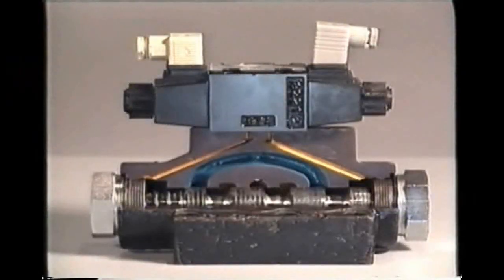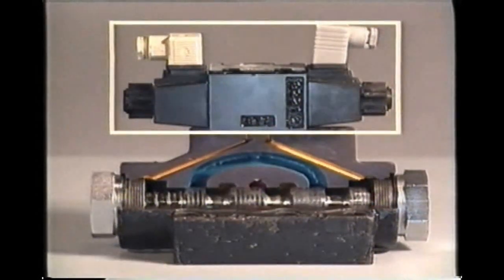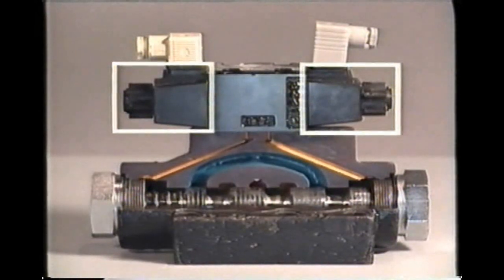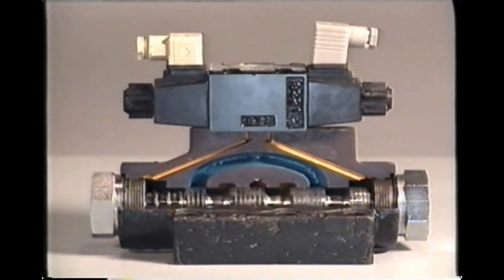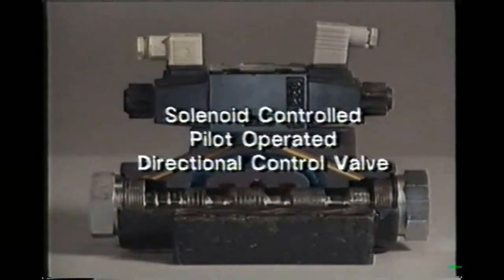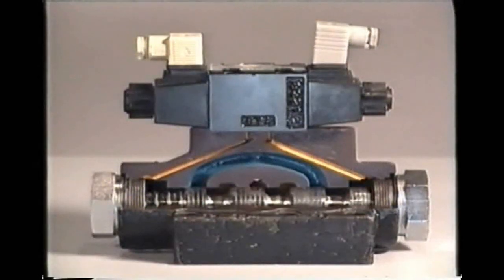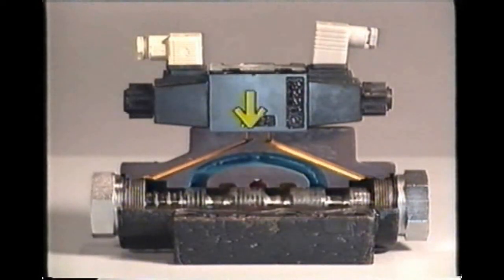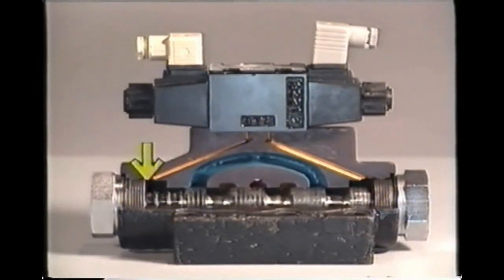When larger size valves are to be electrically actuated, they are usually piggybacked by a smaller valve. The smaller valve mounted directly on the larger valve is operated with solenoids. The hydraulic output of the smaller valve operates the larger valve. Valves like this are called solenoid controlled pilot operated directional control valves. Control of the pilot valve is by solenoid, and movement of the main valve spool is by hydraulic pressure from the pilot valve.